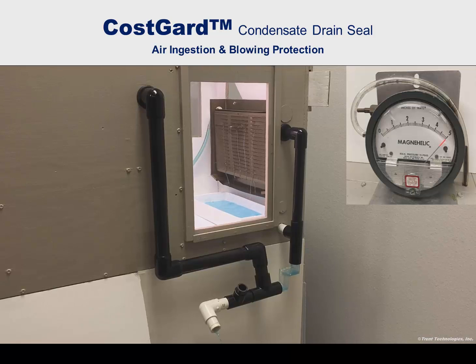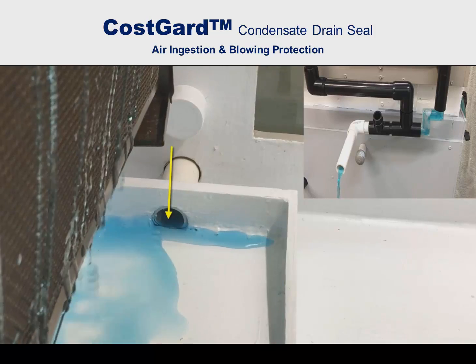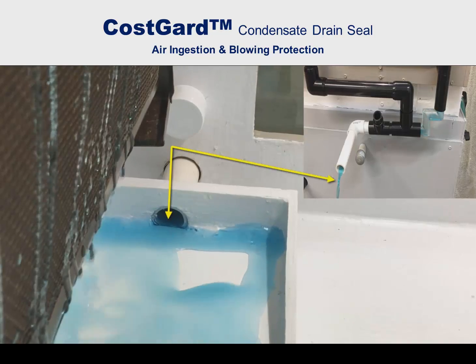CostGard condensate drain seals will operate successfully with internal negative pressures of five inches of water. The CostGard device being demonstrated here is operating at a negative pressure of 1.5 inches of water, typical of air conditioning systems up to 30 tons. Note the two views. Observe that there is no blowing of condensate and that flow discharge is smooth.